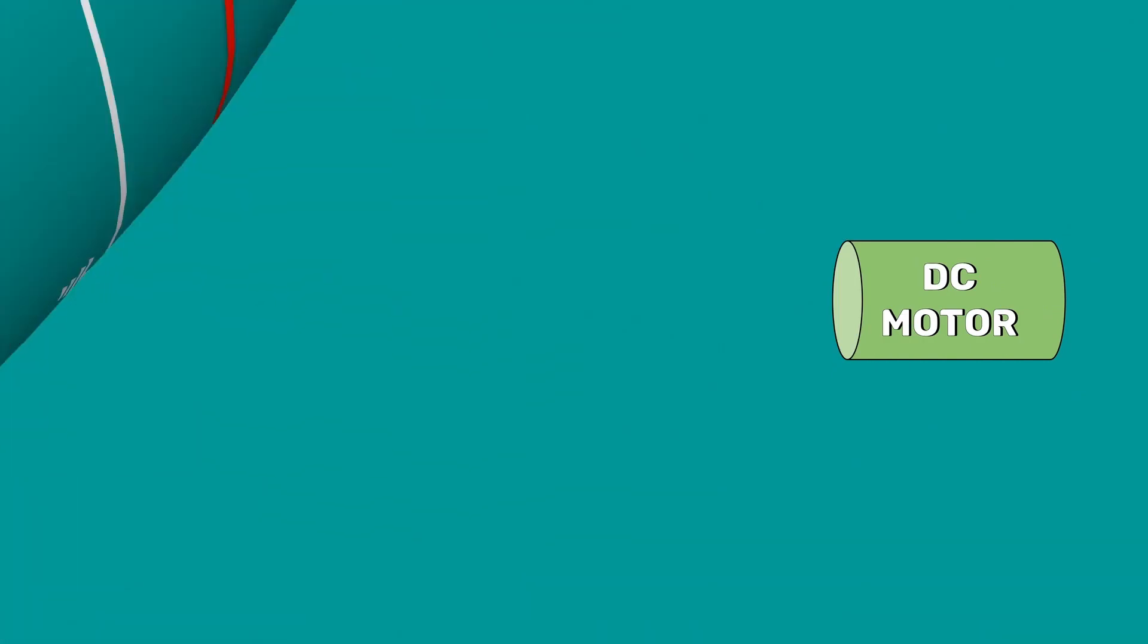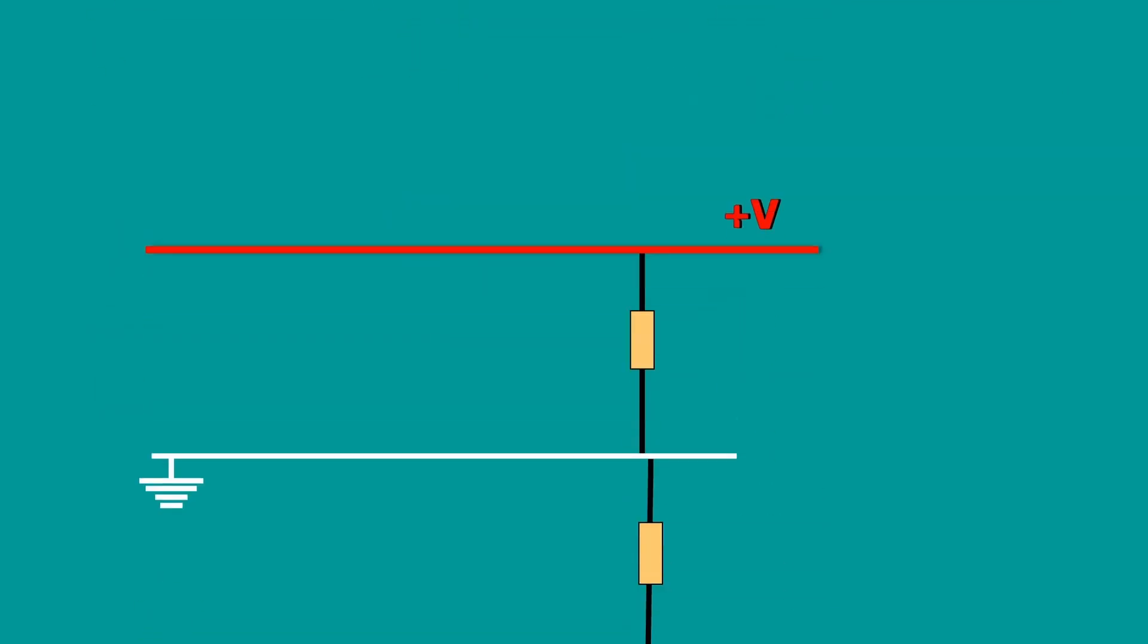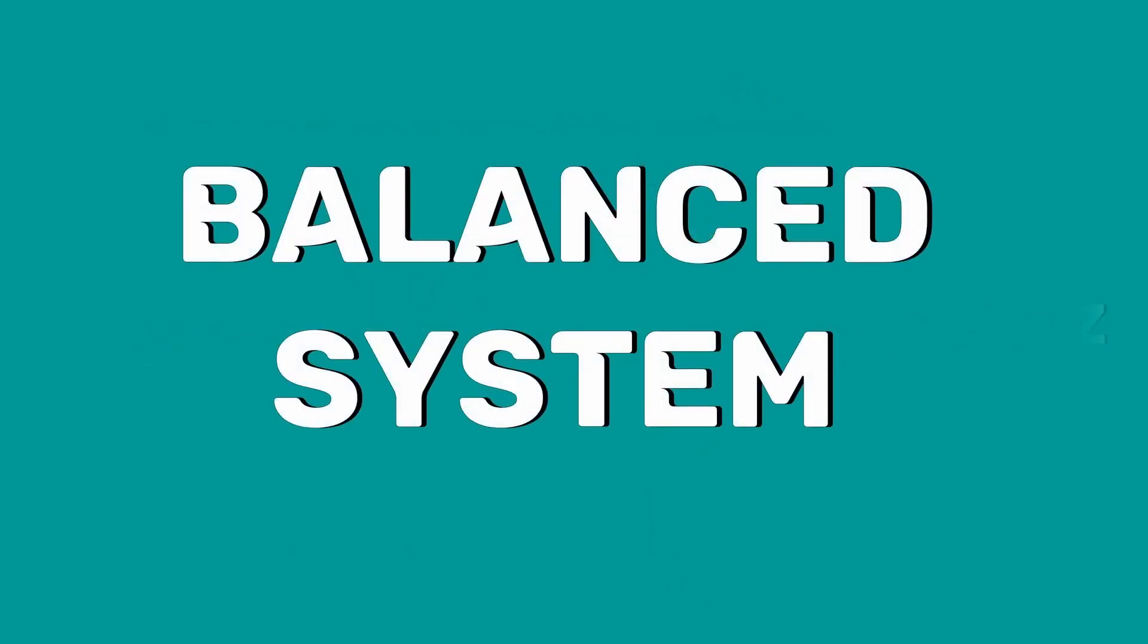The voltage between the positive and the negative conductor is twice the voltage between the outer and the neutral. Motor loads that require high voltage are connected between the positive and negative conductors, while lighting loads which require less voltage are connected between any one outer and the neutral. The current in the neutral wire will depend upon the loads applied to the two sides. If the load applied to both sides of the neutral are equal, then the current in the neutral wire will be zero. This is called a balanced system.